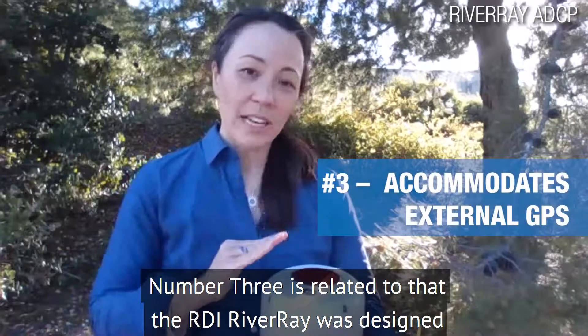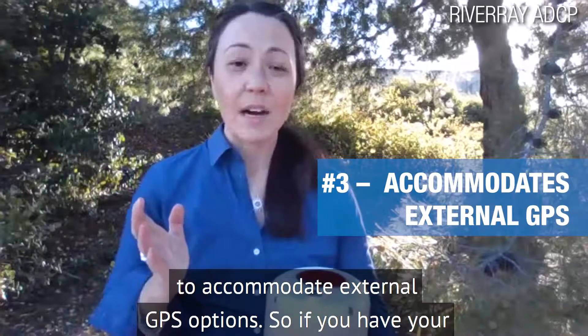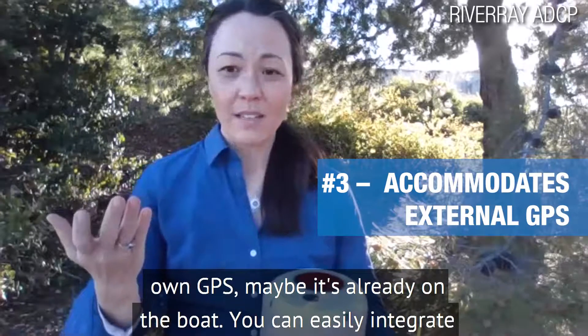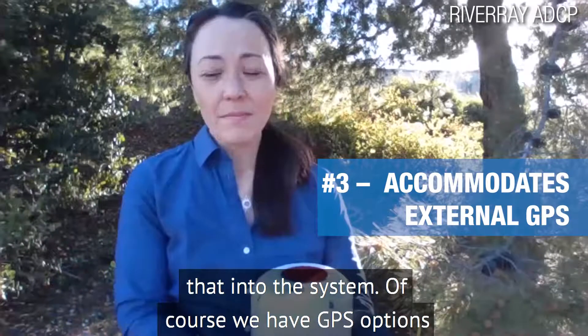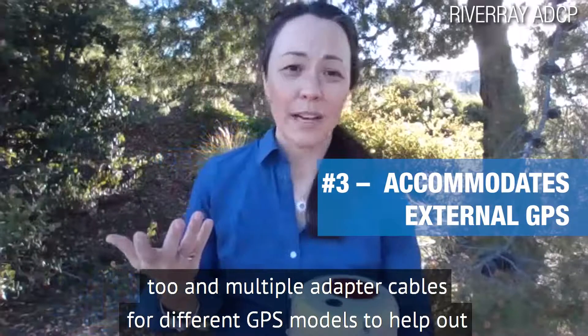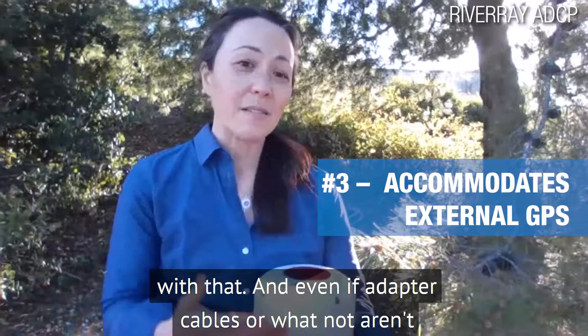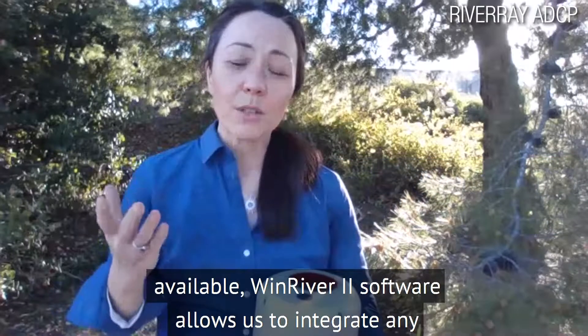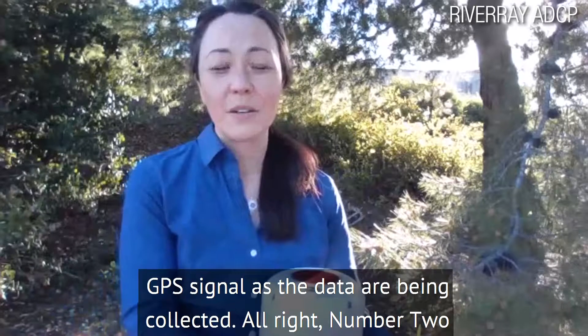Point number three is related to that. The RDI RiverRay was designed to accommodate external GPS options. If you have your own GPS — maybe it's already on the boat — you can easily integrate that into the system. Of course, we have GPS options too, and multiple adapter cables for different GPS models to help with that. Even if adapter cables aren't available, WinRiver II software allows us to integrate any GPS signal as the data are being collected.